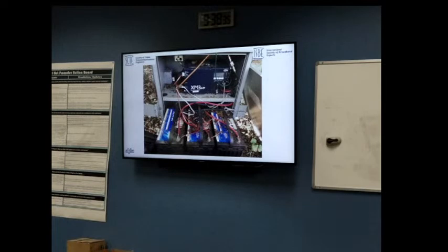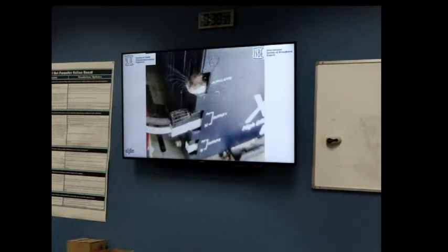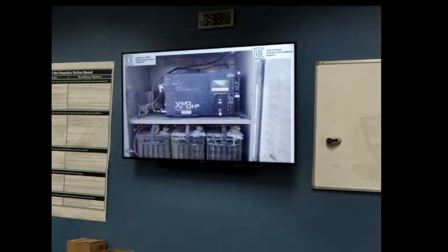And this is the result of different things ending up in the power supply cabinet. And this is a little friendly guy poking his little face out. It does happen. They're nice and warm in the winter. This is what they do inside of it. They make nests, and then corrosion and other things can get in there. There's a lot of different things here. But let me jump back out to the next question.